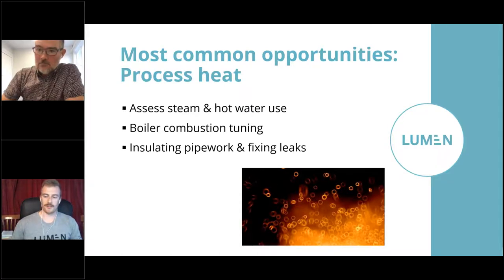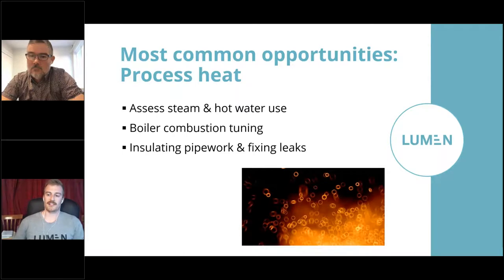The second tip is to make sure your boiler has been tuned to run at the lowest excess air required to still maintain complete combustion. You can often pick up 1 to 3% improvement in combustion efficiency through regular combustion tuning. Again, it's one of those ones between 6 and 12 months generally. And the last thing is to insulate any exposed pipework, particularly steam pipework. It's not only an energy issue, but also a health and safety risk. It's pretty easy to burn yourself on an exposed steam pipe. And also fix any steam or hot water leaks. Again, not just an energy issue, but you'll also be reducing your water consumption and your water treatment costs.